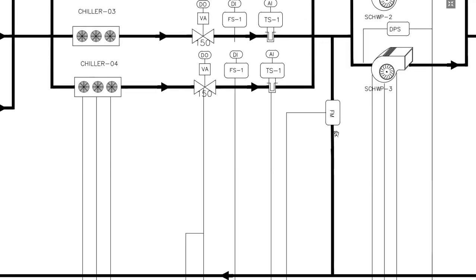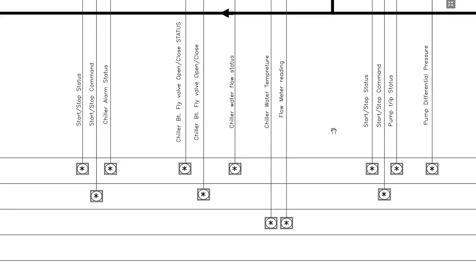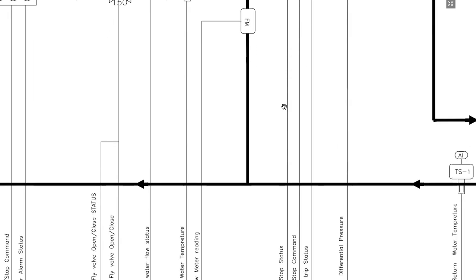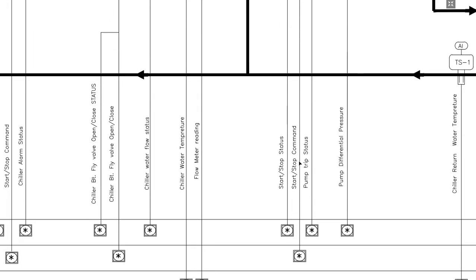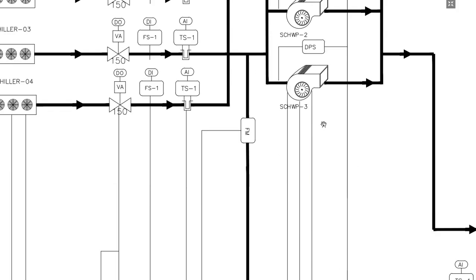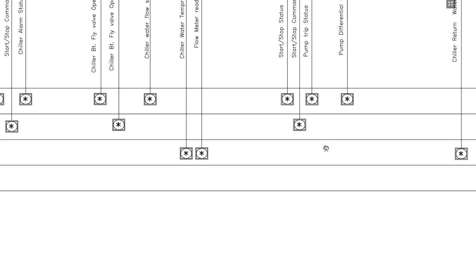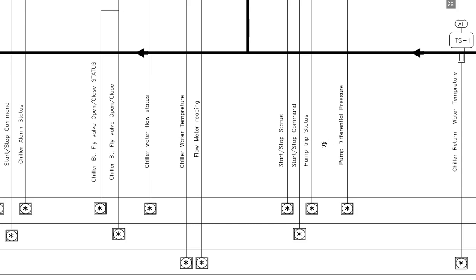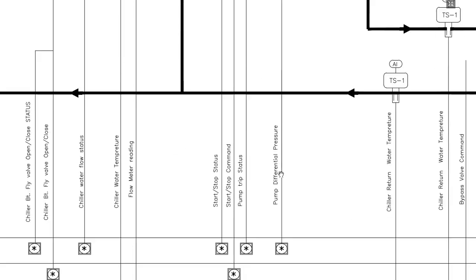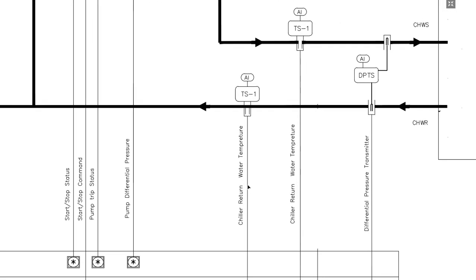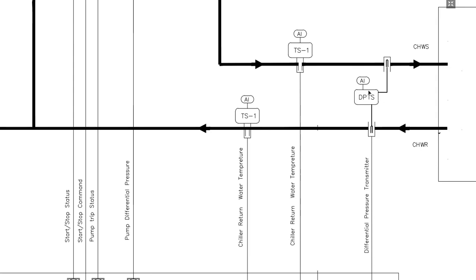On the decoupler line, a flow meter is installed, and we are reading its value using an analog input point. Then we have secondary pumps where we give start/stop command and monitor the status and trip status. Note that VFD points are not shown here, but since this is a primary-secondary chilled water system, there must be a VFD, and we shall have two additional points for VFD speed control and VFD feedback. Then we have a pump differential pressure switch similar to the primary chilled water pump, return chilled water temperature, chiller supply temperature, and a differential pressure transmitter to monitor the differential pressure between the main supply line and the main return line.